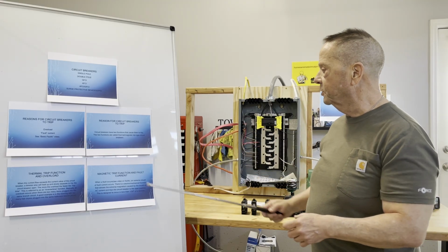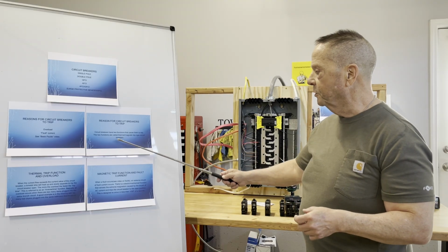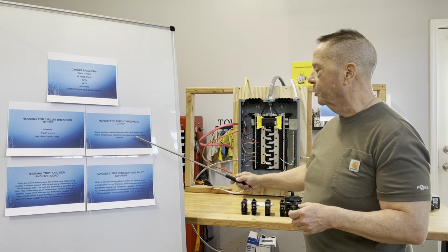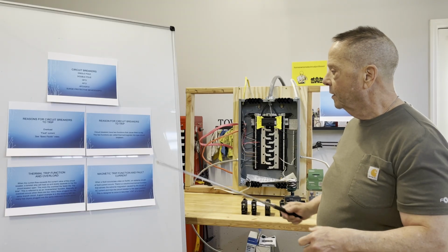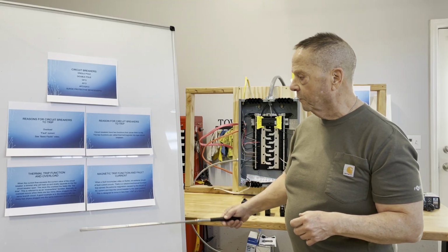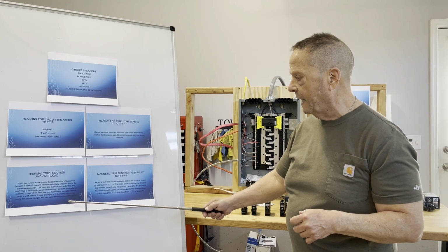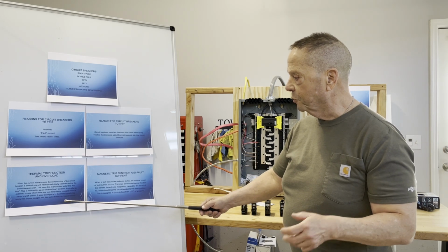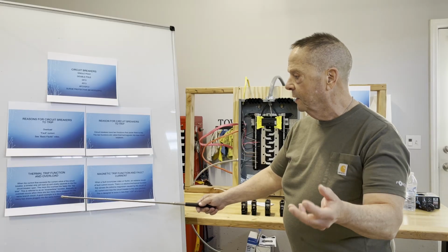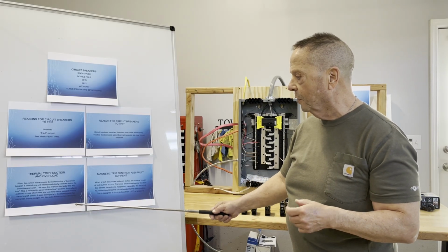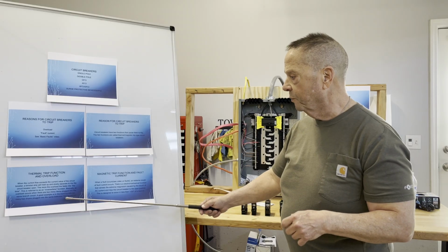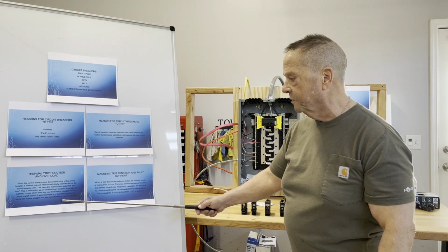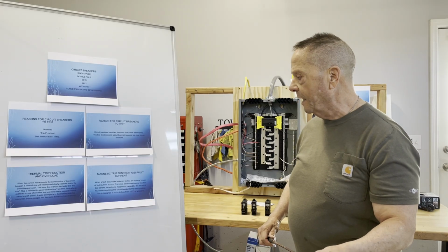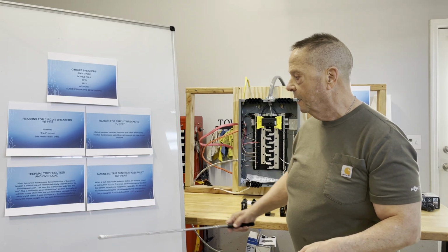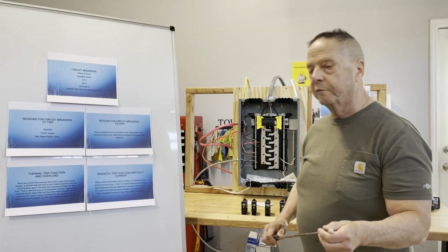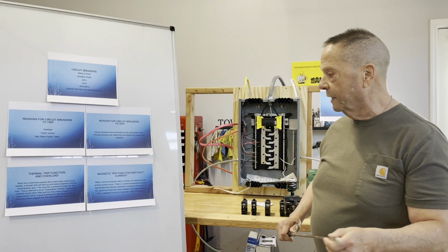Circuit breakers have two functions that cause them to trip. The two functions are called thermomagnetic type circuit breakers. The one thing that will cause them to trip is an overload. When the current flow exceeds the current value of the circuit breaker, there's a bimetal strip, it heats up, it slowly separates, and it opens the circuit breaker. The more the overload, the faster the trip time. This is referred to as inverse time function. Basically, an overload occurs when there are too many items plugged into the same branch circuit.